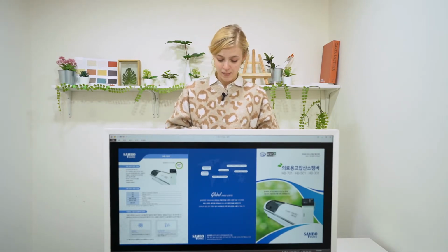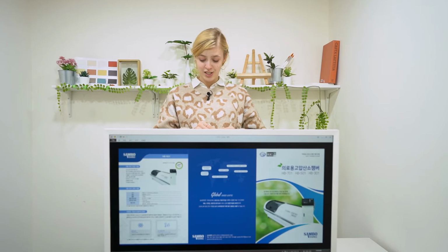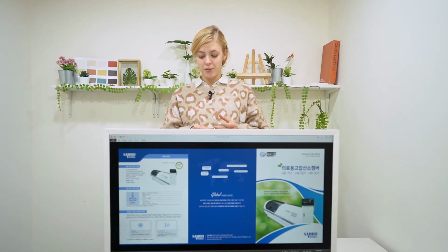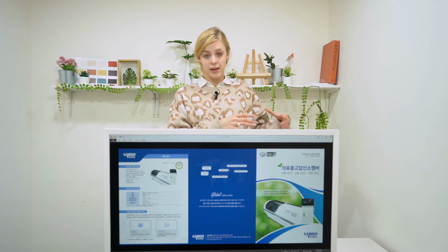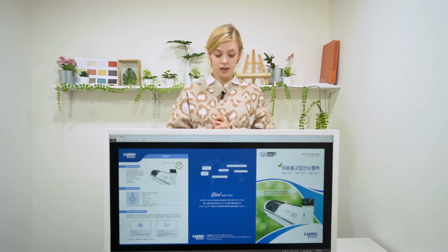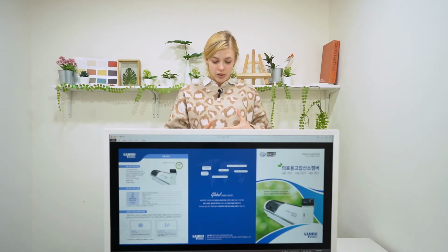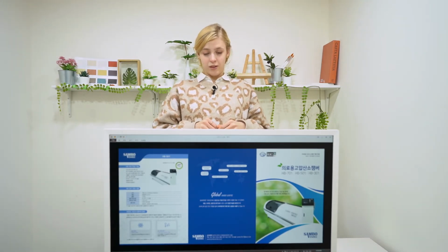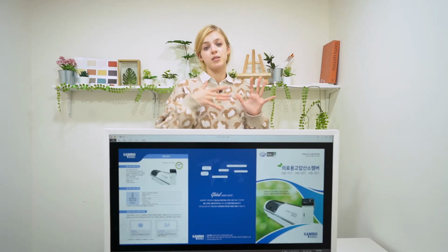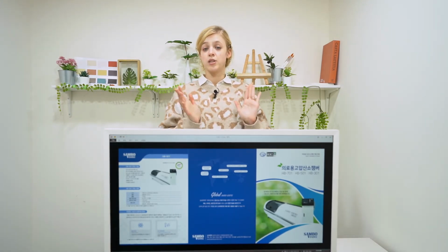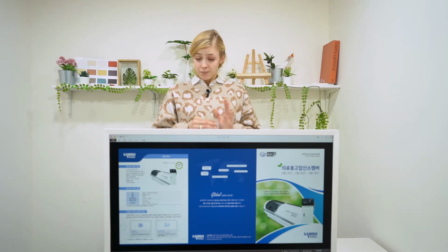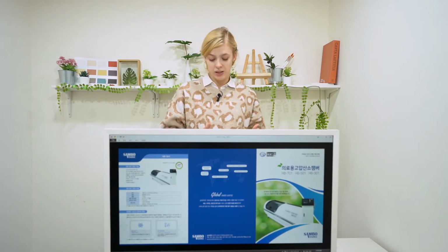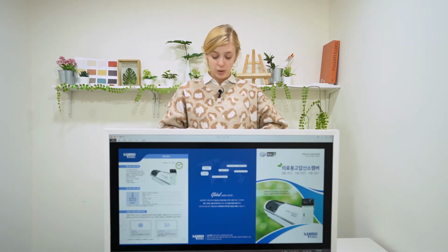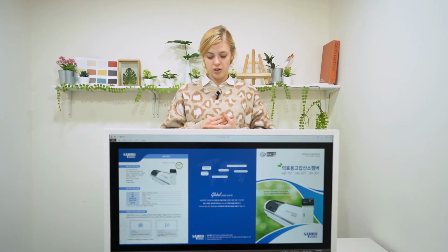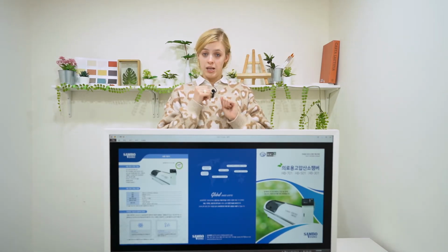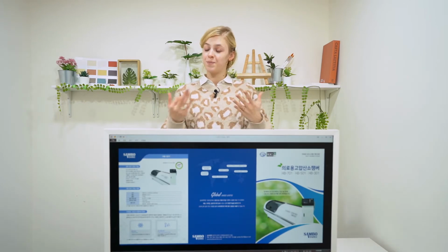A system of emitting carbon dioxide inside a medical high pressure oxygen chamber, and a method of emitting carbon dioxide using it was the patent that the chamber got. And the internal and external emergency decompression valve is very new for this type of chamber as well. It has like a one-touch screw method, which is absolutely genius and very convenient for the person using it.